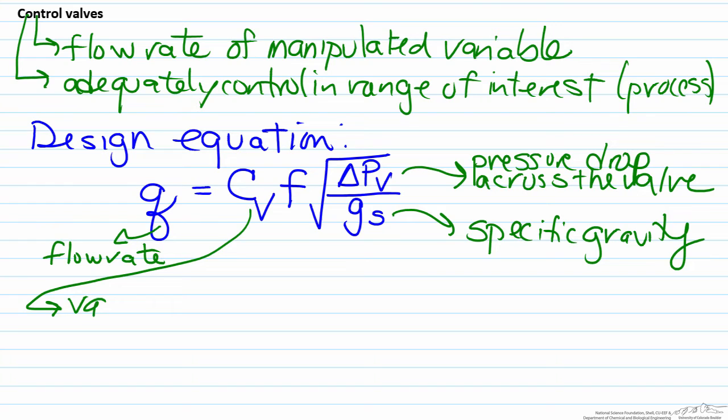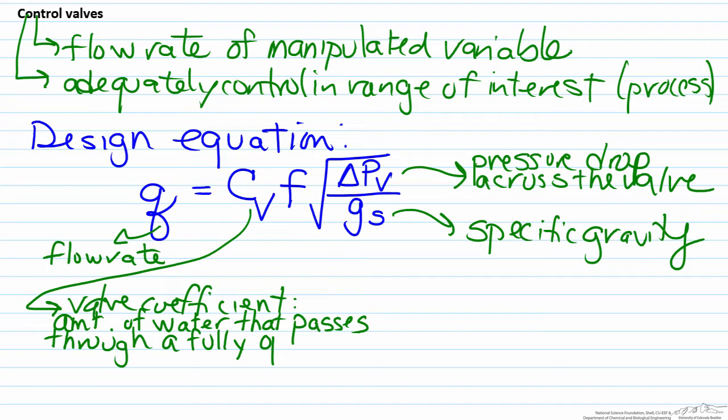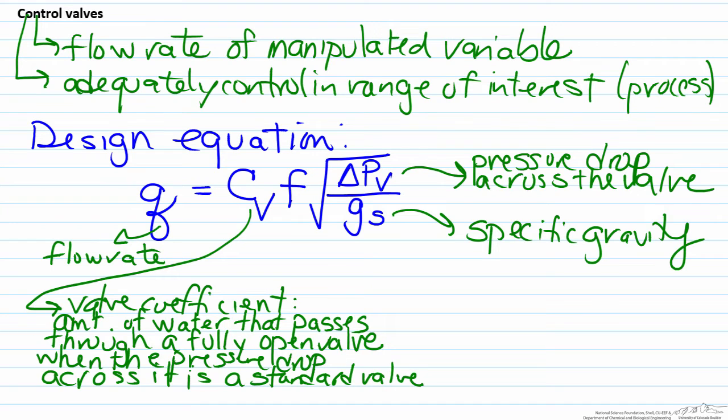CV represents the valve coefficient, and the valve coefficient is an explicit definition. It represents the amount of water that passes through a fully open valve when the pressure drop across it is a standard value. Depending on your units this can be different, but typically one example of a standard value would be one psi.